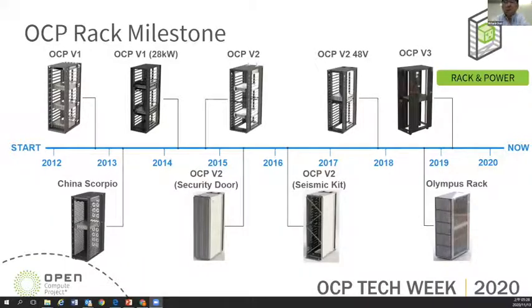So Delta has developed a series of open rack products, including the power supply, PDU, power shelf, PDU rack, and the rack manager. Starting from 2012, we developed the V1 open rack, and it helped us understand the data center IT rack design concept. After that, some customers asked us to leverage the open rack to design IT racks for them, like we did for the Scorpio, where we put firmware on it, and we also tried to increase the V1 open rack power to 28 kilowatt.